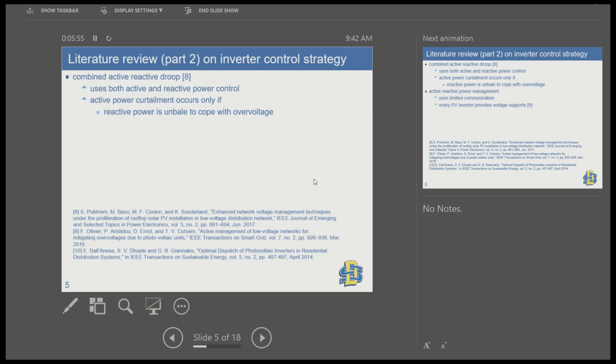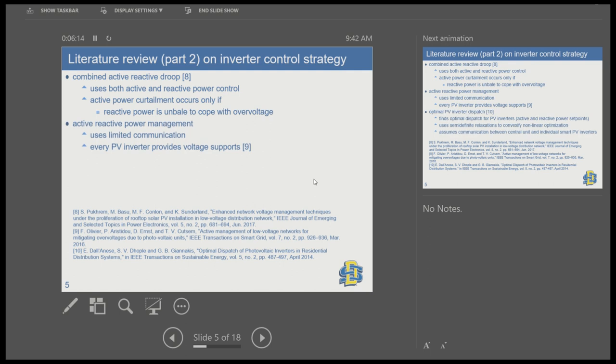Another approach is combined active and reactive power control. In that approach, they first do reactive power absorption to control the overvoltage, and only if it is not sufficient do they apply active power curtailment. That way we minimize the amount of energy curtailment needed to prevent overvoltage and save money.